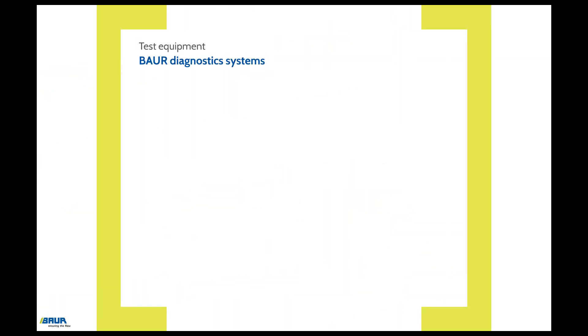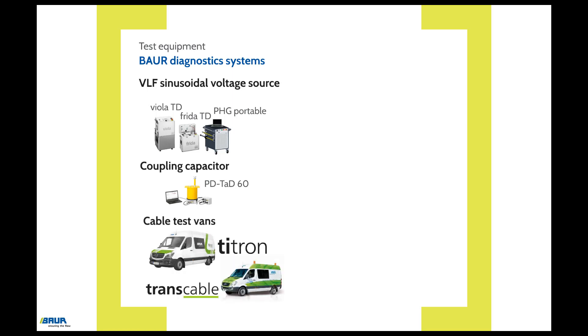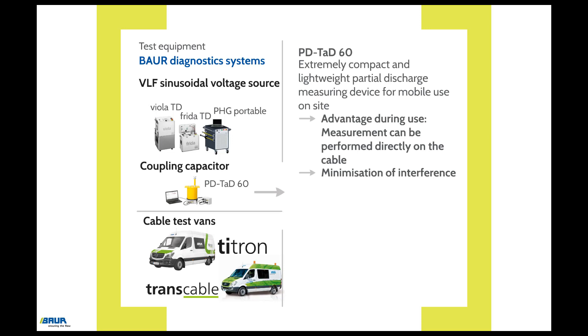To perform measurements like the one described in the example, a VLF sinusoidal voltage source is required, such as FridaTD, ViolaTD, or PHG from Baur. With the PD-TaD 60 partial discharge diagnostic system and a PC to control it, the measurement of the dissipation factor and partial discharges can be performed in parallel. The PD-TaD 60 represents the most compact and lightweight partial discharge measuring device for mobile use on site. This portability makes it possible to perform the measurement directly on the cable, which minimizes interference and thus represents an important precondition for precise and meaningful measurement results.